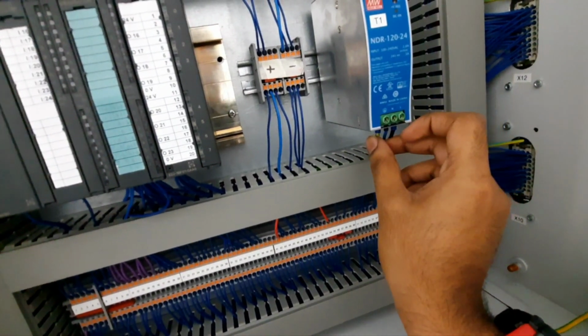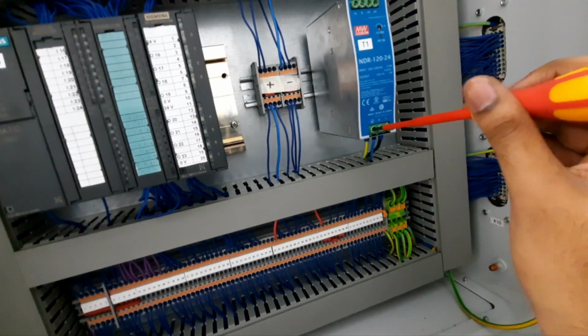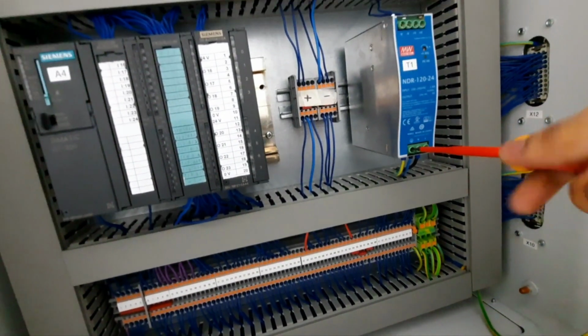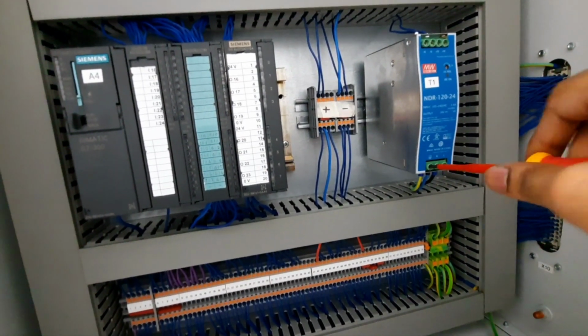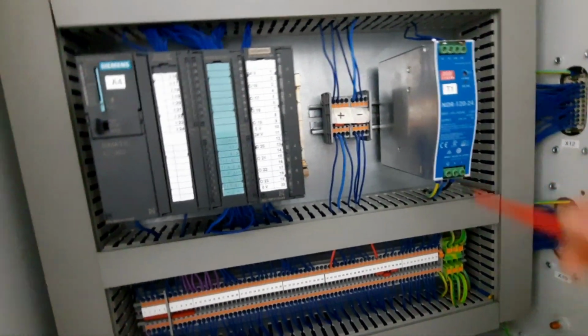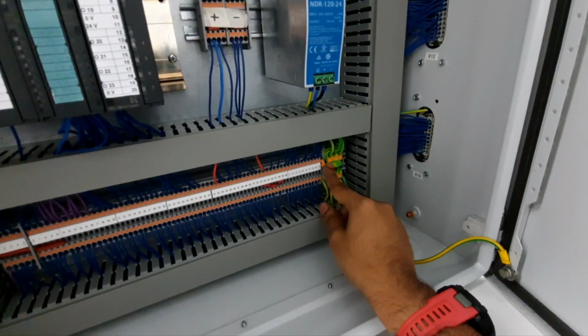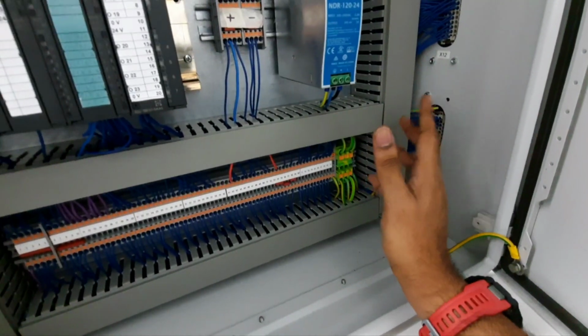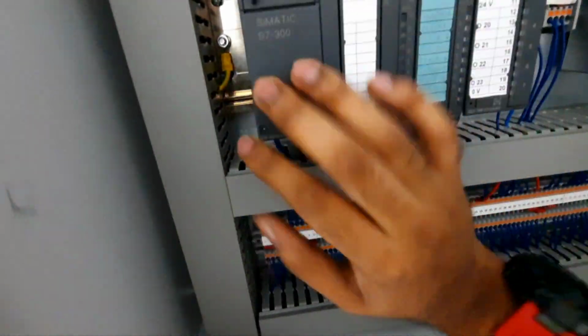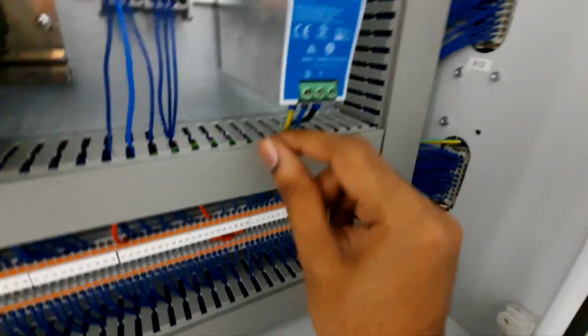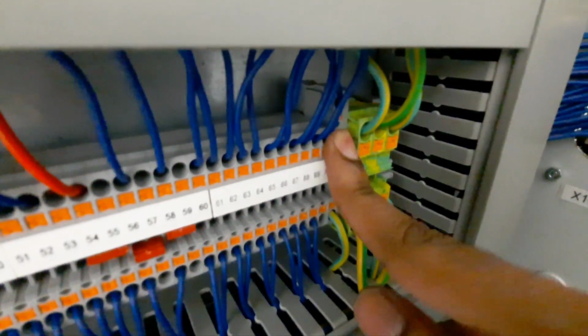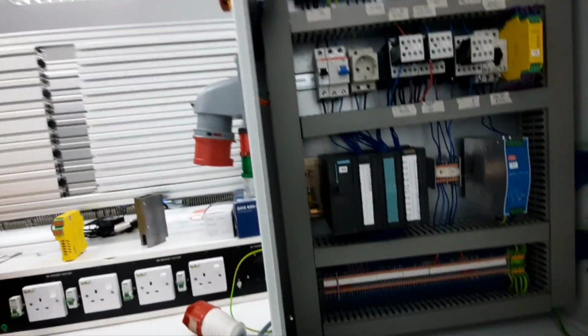Then your PE here, and then this one - so three things back again. After you've done your insulation test, your PLC must be plugged in already, your PE for the transformer plugged in, and your X1 terminal put back in place. Then you're ready to go, the system is ready. Now this one I have to plug out.